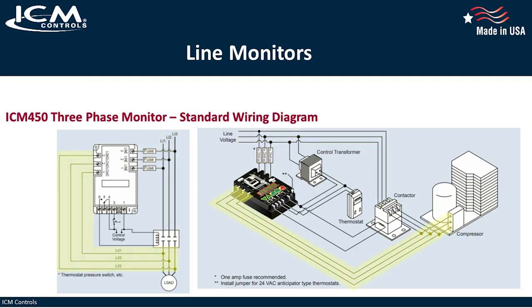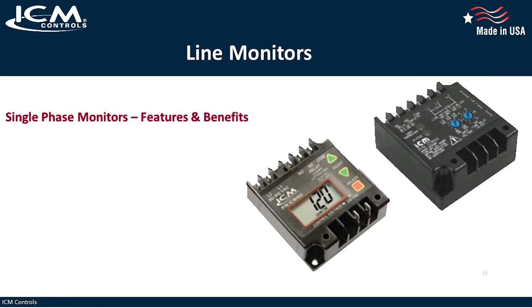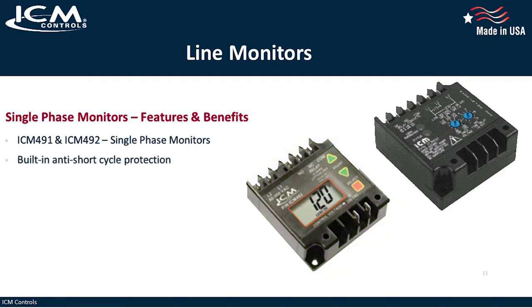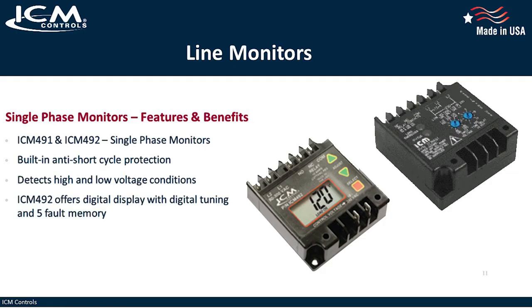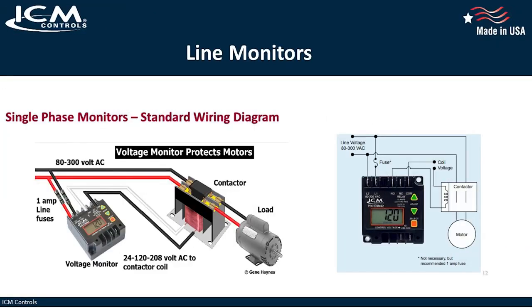In addition to three-phase line voltage monitors, ICM also offers single-phase line voltage monitors, namely the ICM 491, and its digital counterpart, the ICM 492. You don't have to worry about voltage imbalance when you're dealing with a single phase, but you do have to pay attention to the high and low voltage conditions and rapid short cycling caused by transient faults and power interruptions. The ICM 491 and the ICM 492 are great low-cost add-ons that give you that extra layer of protection and peace of mind. Like their three-phase big brothers, the single-phase units are also wired in parallel and monitor the line power coming into the circuit.